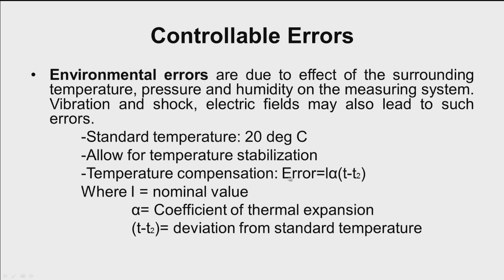The compensation can be calculated using the relationship: Error = L × α × (T − T₂), where L is the nominal value, α is the coefficient of thermal expansion of the workpiece material, and (T − T₂) is the deviation from standard temperature. If T is 20°C and T₂ is 22°C, then the deviation is 2 degrees. Using this relationship, we can calculate the error due to environmental factors and account for it when giving measurement results.